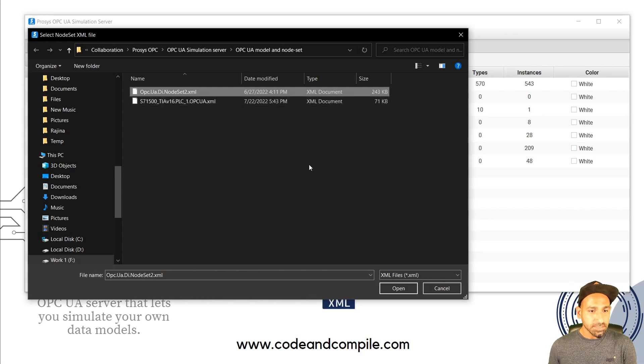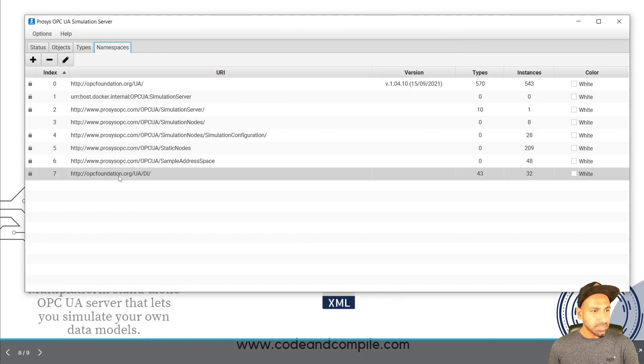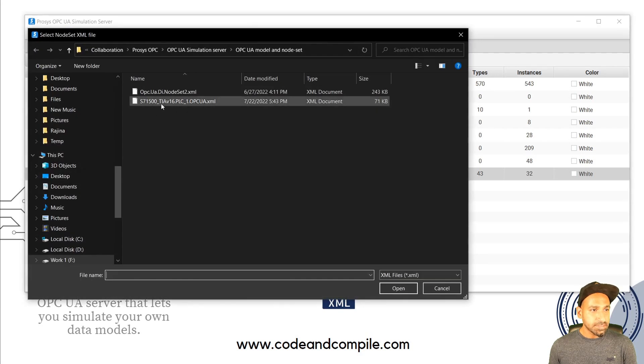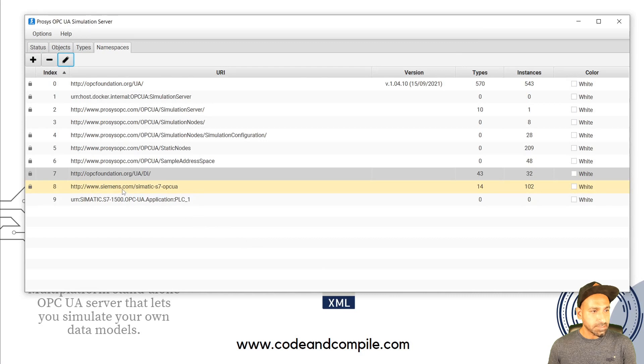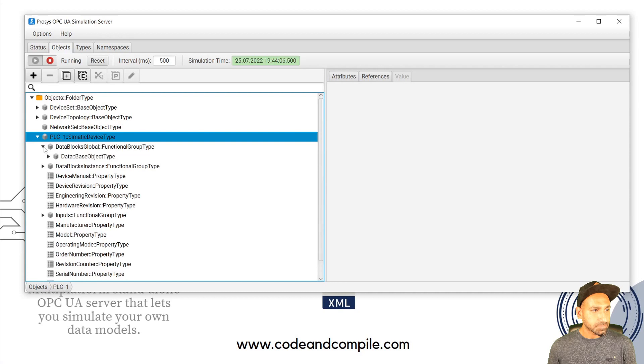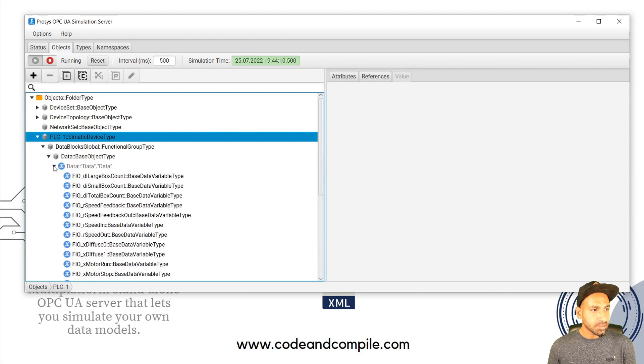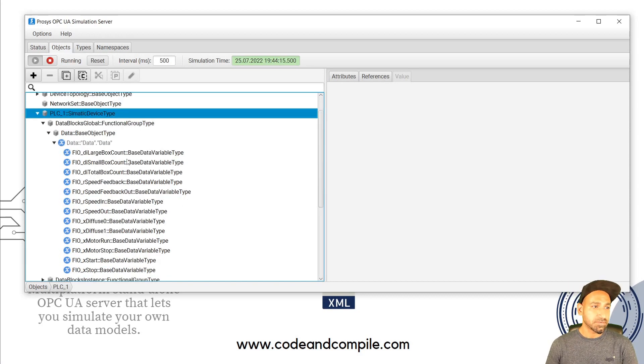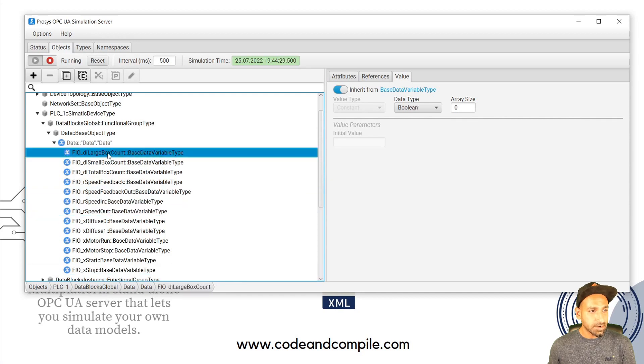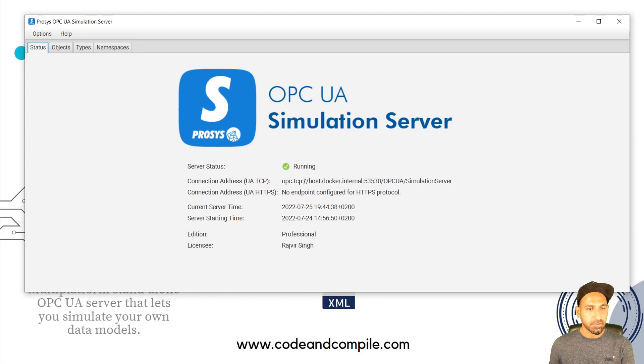This first step — importing the Siemens node set — is always required when importing from a Siemens PLC. Click Open and you'll see OPC Foundation UA DI is listed. Then click Plus again and Import Node Set, selecting the XML file you exported from TIA Portal. Import it into the simulation server, and you'll see it listed as S7 OPC UA. Now go to Objects and you'll notice the PLC is defined there. Under Global Data and Data, you'll find all the tags — all imported into the simulation server. This is not real-time from the PLC; you can disconnect the PLC, and all these variables are accessible via the OPC UA simulation server.